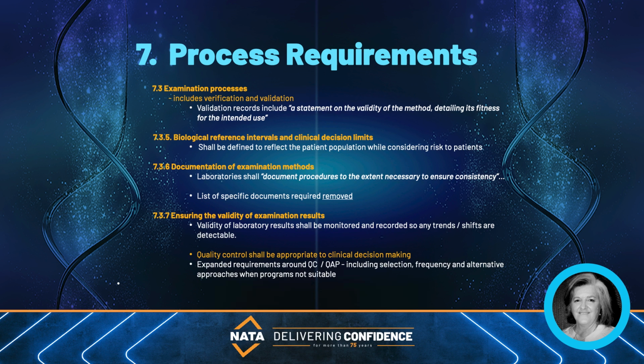Labs shall validate developed methods or methods used outside their original intended purpose. The validation shall be as extensive as is necessary and confirm that the requirements for the intended use of the examination have been fulfilled. Staff with the appropriate authorization and competence shall review validations, and records shall indicate a statement on the validity of the method detailing its fitness for intended purpose.